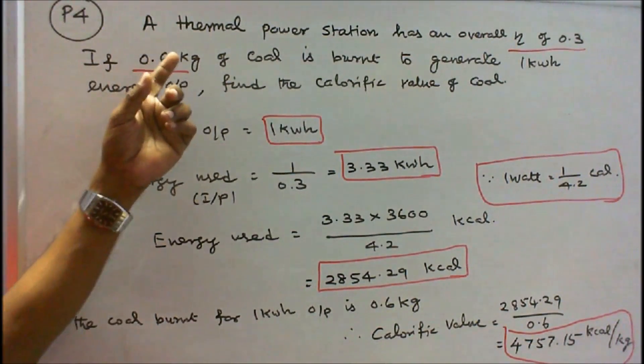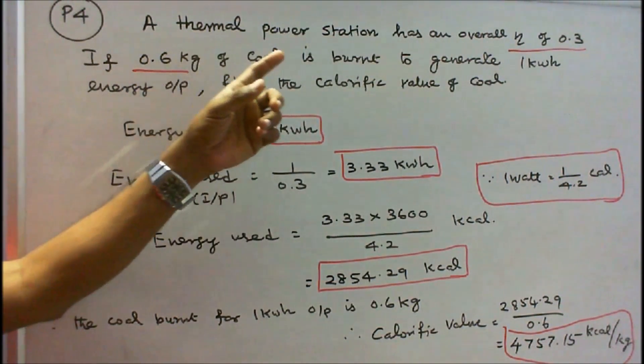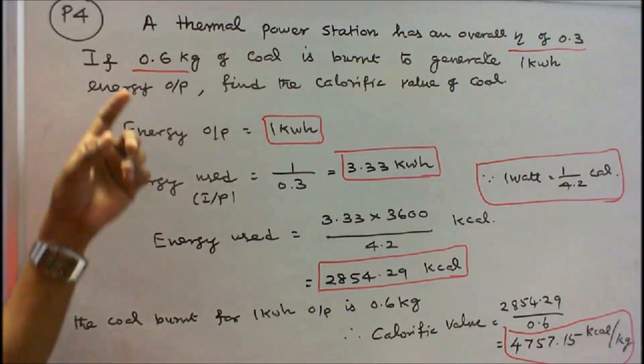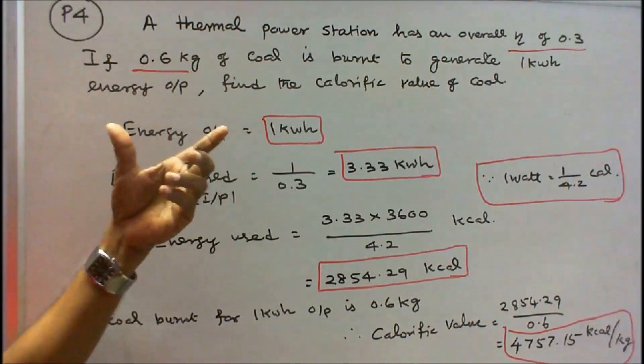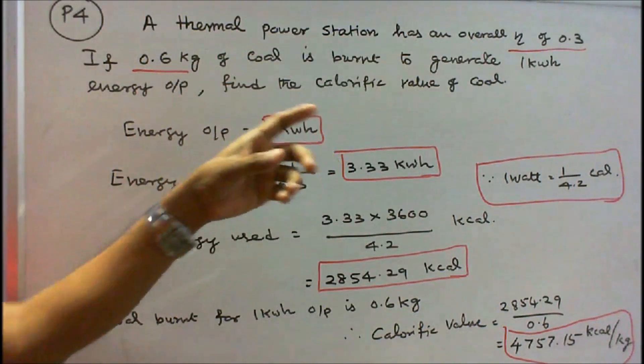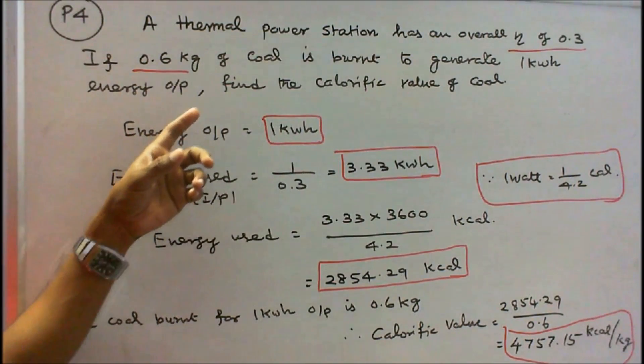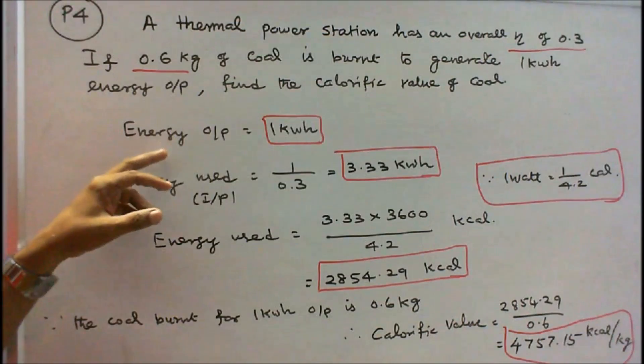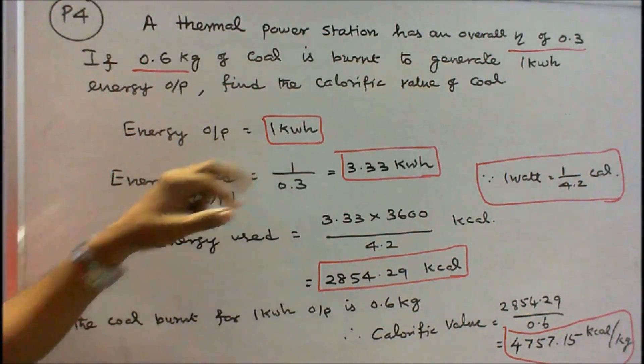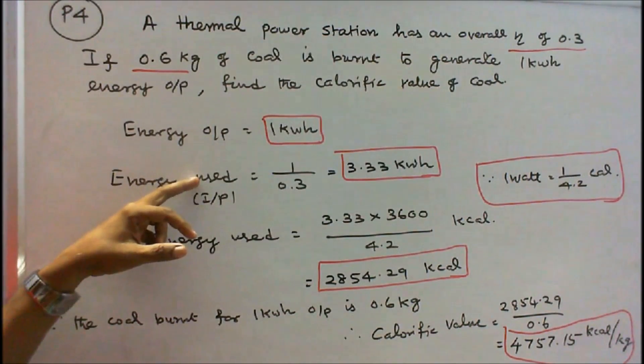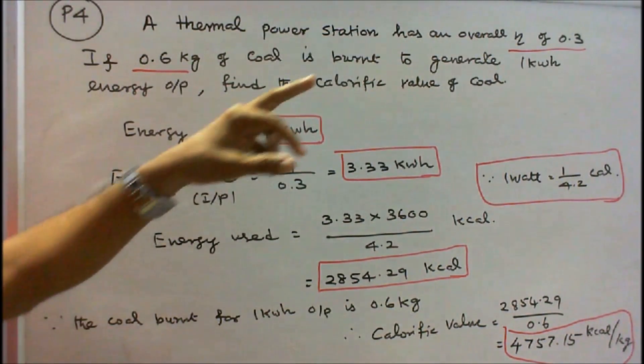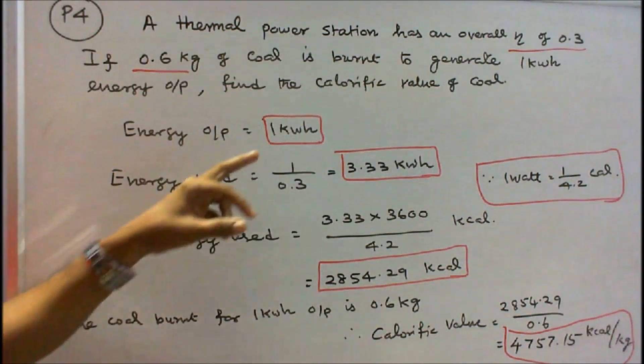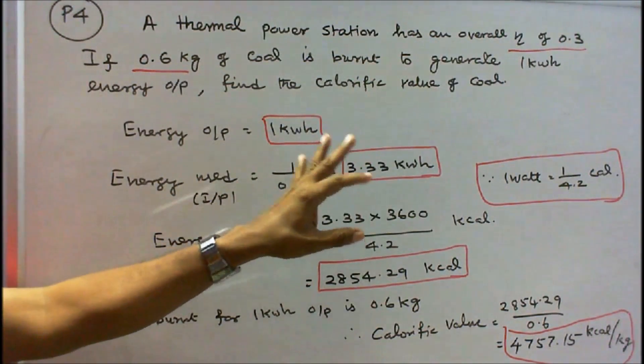Problem number 4: a thermal power station has an overall efficiency of 0.3. If 0.6 kg of coal is burnt to generate 1 kilowatt-hour energy output, find the calorific value of coal. Energy output = 1 kilowatt-hour. Energy used = energy output ÷ station efficiency = 1 ÷ 0.3 = 3.33 kilowatt-hours.